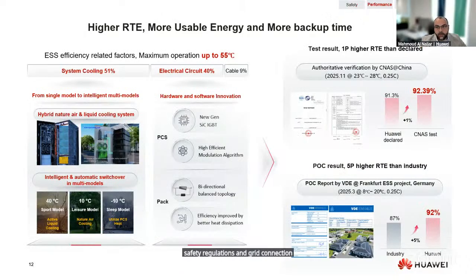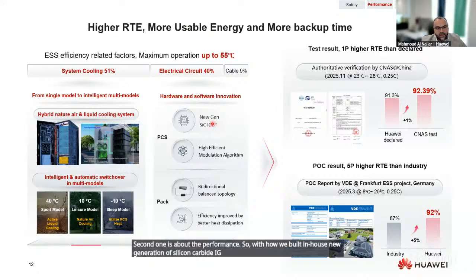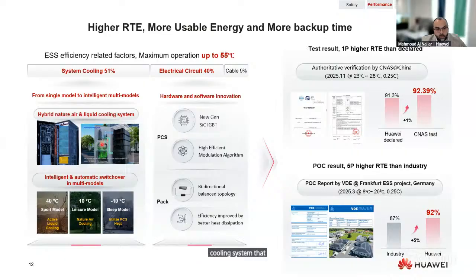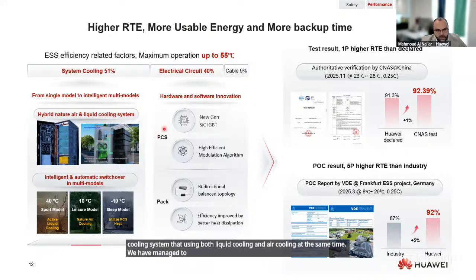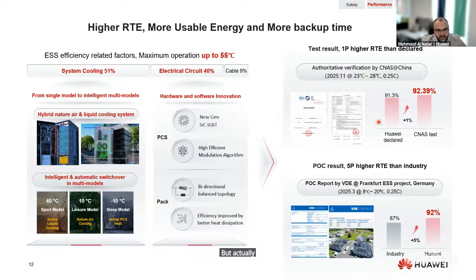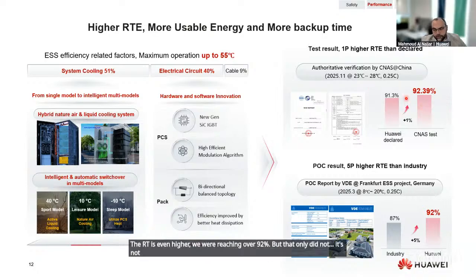Second one is about the performance. So with Huawei built in-house a new generation of silicon carbide IGBTs and our innovative cooling system that uses both liquid cooling and air cooling at the same time, we have managed to reach the highest round-trip efficiency in the industry of 91.3%. But actually, in the actual testing at sites in multiple locations, the RT is even higher. We were reaching over 92%.